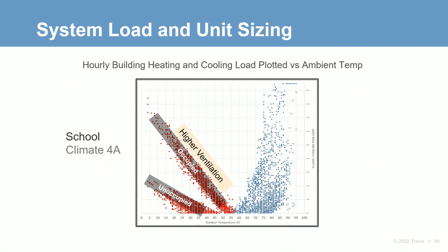It is well understood that 100% cooling capacity is not often needed. This is even more true for heating. Notice the point density near the peak hours, the green circles. Hours near peak load are very few for cooling, but even fewer for heating.